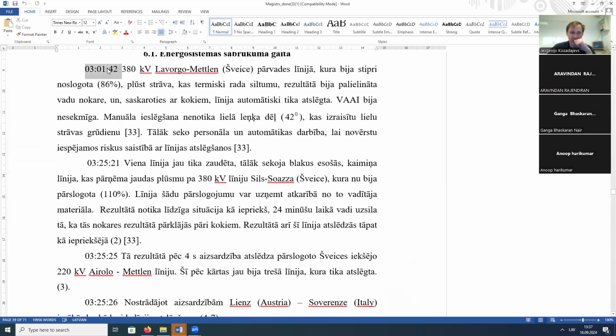Let's see the timing. This is 3 o'clock p.m. Sorry, a.m. It's after midnight, it is in the night. 24 minutes later, we lost one line. It means that all other lines had more overload, and as a result, one more time, due to the overload, a 380 line from Switzerland disconnected as well, because it was overloaded by 10%. The total load is 110%. So we lost one more line.